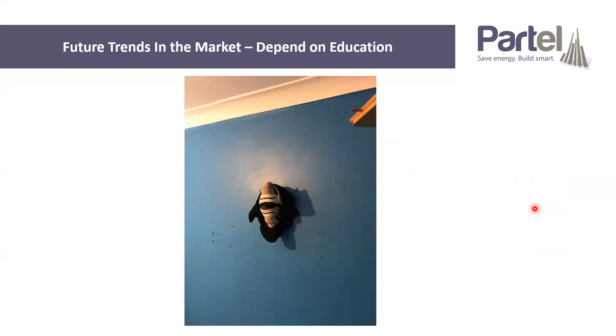I just wanted to finish with this image — it's a strange one that came up. We're doing some retrofit work for Dublin City Council on their housing stock, which involves going in, doing surveys with homeowners, checking humidity and mould issues, and then coming up with a ventilation strategy. I think the future trends of the market are going to depend on homeowner education. Shane, one of our colleagues, sent this into our group chat — if you're wondering what that is, that's a background vent stuffed with a T-shirt and a pair of runners so that no air can get through it. We really need to focus on education. When you're in the industry, it's easy to believe that everybody is on board with ventilation and understands the importance of it, but this is the type of thing we're still seeing on the ground in reality.